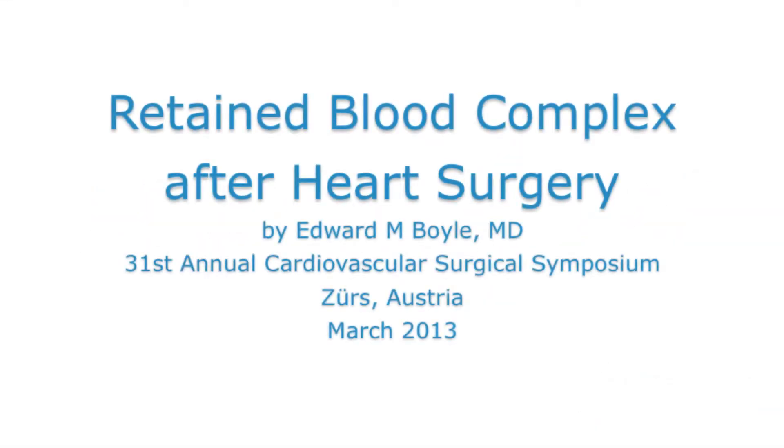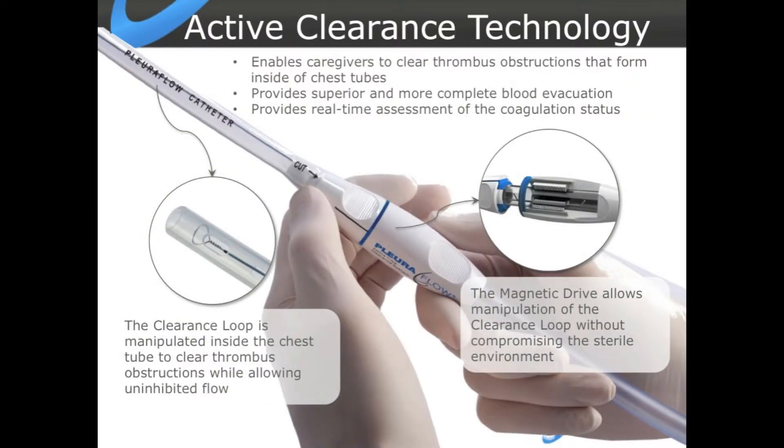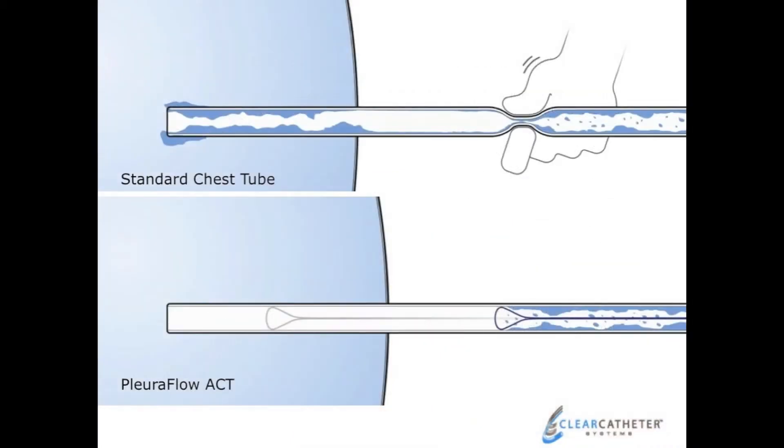Ultimately, we developed this PleuraFlow active clearance technology system. It's basically a standard chest tube that has a clearance mechanism to keep it open. The mechanism has a guide wire with a loop, and then there's a magnetic system from external to internal that allows you to move that guide wire in and out of the tube.